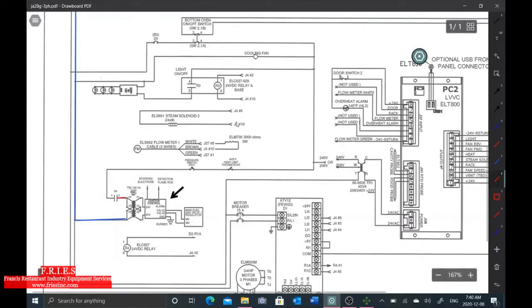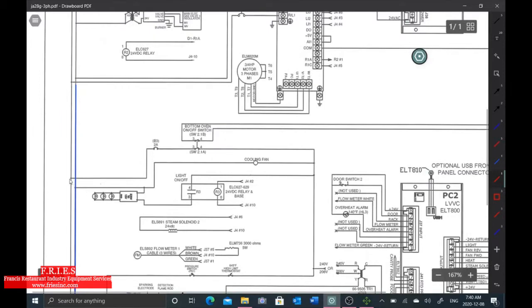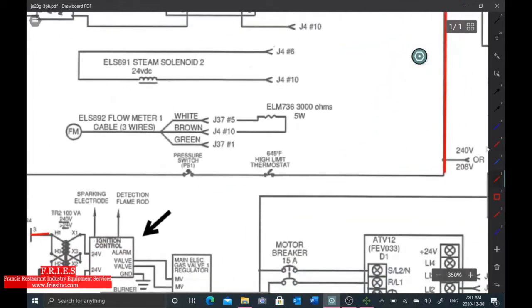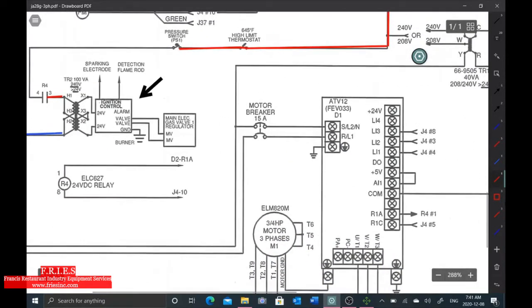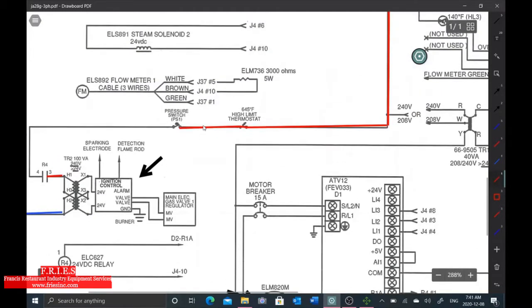Okay, so here's what our sequence is. So I'm going to draw it coming in. So we come off our L1. We have a little 2 amp fuse breaker switch. Then we have our switch here. And then once we come through our switch, we come here. And then we come to our high limit right here. High limit closes, it sends power to our pressure switch. Okay, our pressure switch here is connected to this motor. So if this motor's running, this switch right here should be closed.